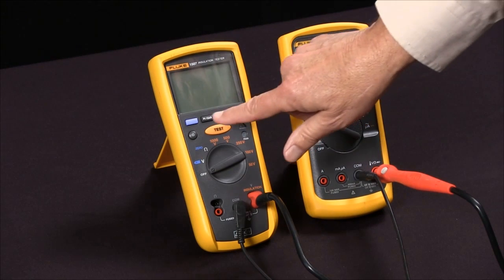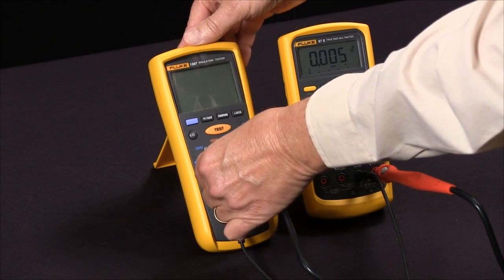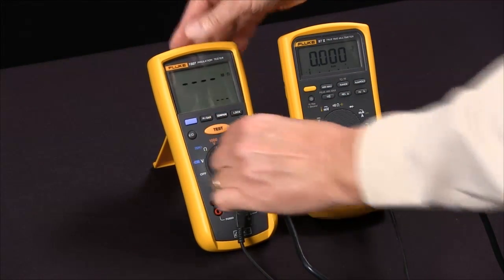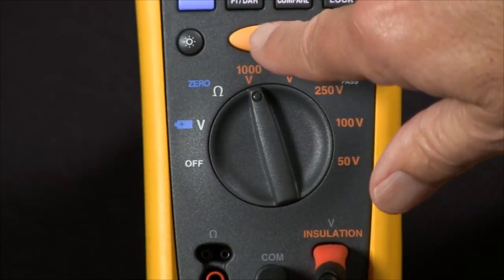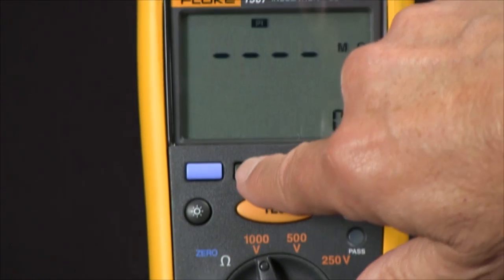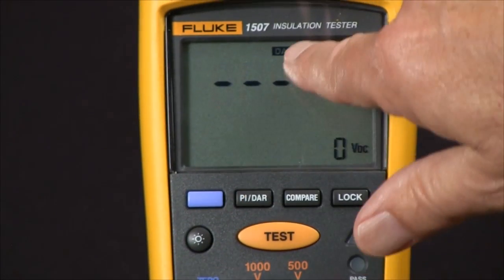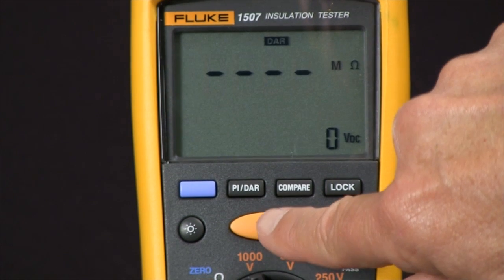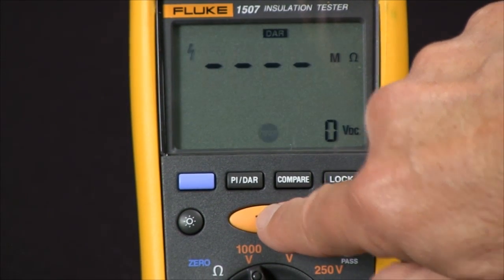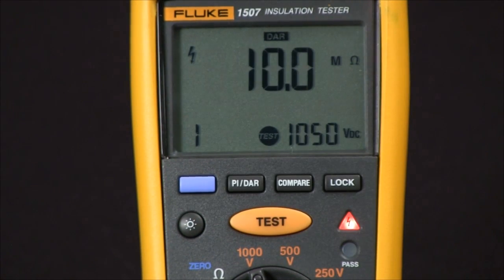We're going to pick 1,000 volts, so we rotate our selector knob to 1,000 volts and select our test. In this case, I'm going to do DAR, dielectric absorption ratio, and I push the test button, and it begins the test.